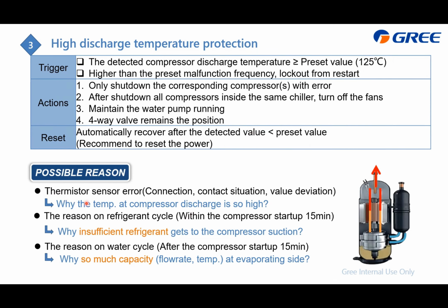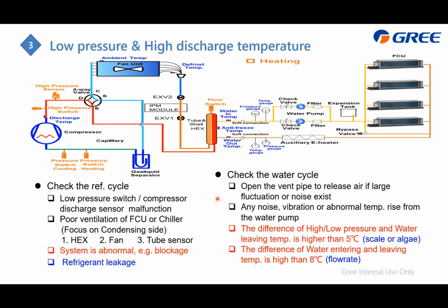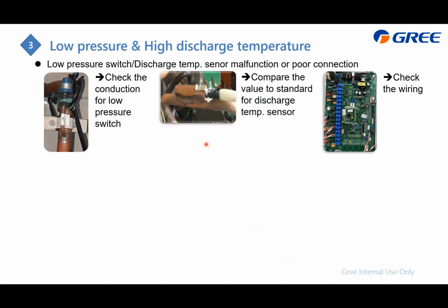And the checking method is, of course, first to check whether the temperature of the compressor discharge is really so high or not. Within 15 minutes of compressor start up, just focus on the refrigerant cycle. And after 15 minutes, focus on the water cycle. The detail, and this time I make it heating. This is the heating cycle. To check the refrigerant cycle first, it is all very similar to the high pressure protection, and the difference is just here. Maybe there's refrigerant leakage. Here is the detail. I just focus on the different points.